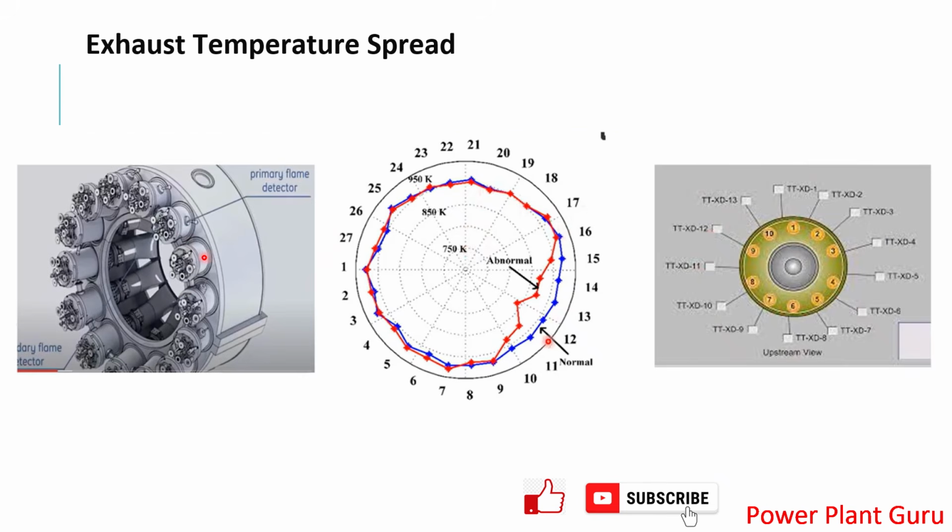If you pass the same amount of fuel and the same amount of regulated air through all these combustion cans, in a circular periphery, then the combustion you monitor at the aft end of your combustion system should show similar, equal behavior across all the temperature sensors or thermocouples that monitor the exhaust temperature.